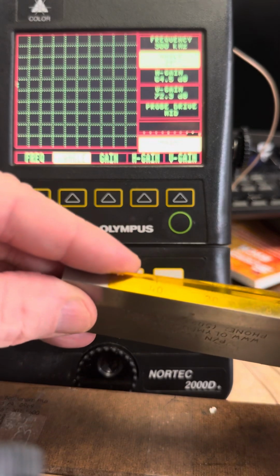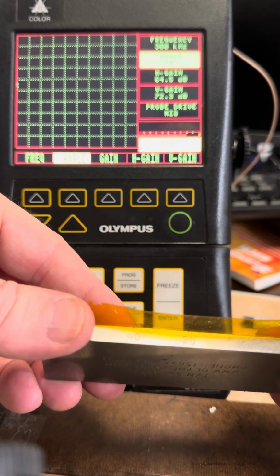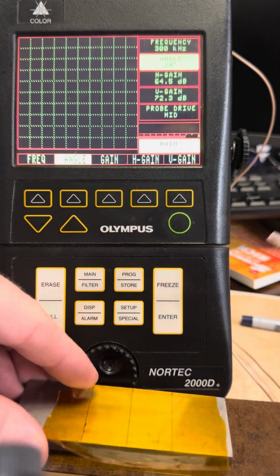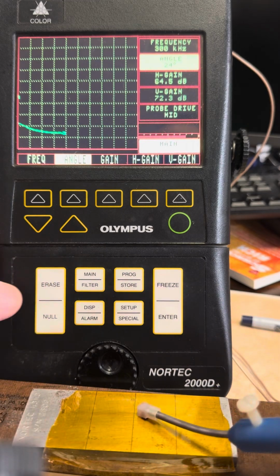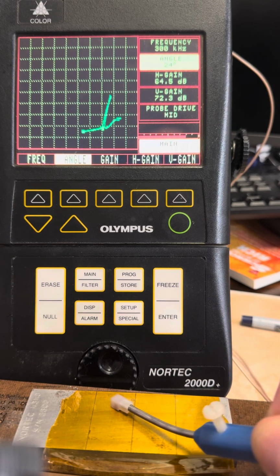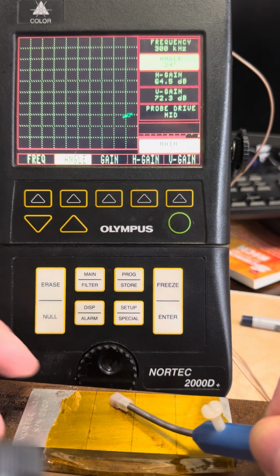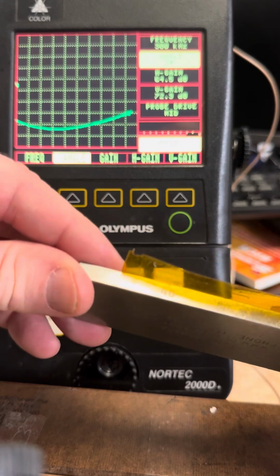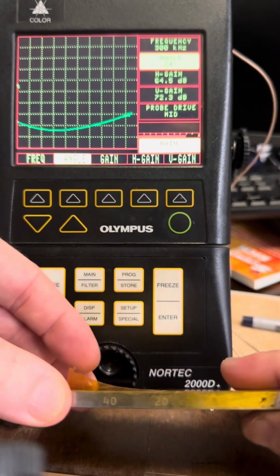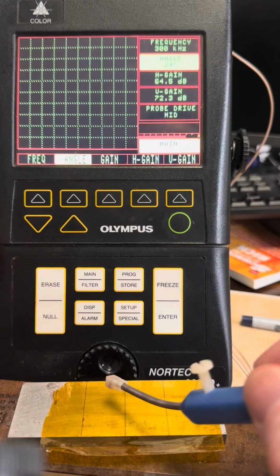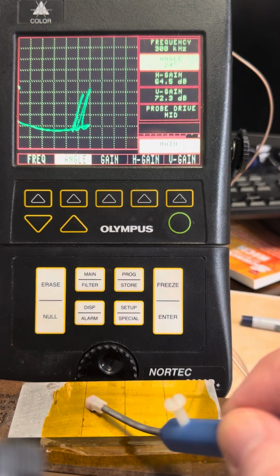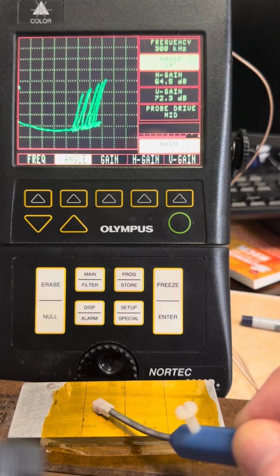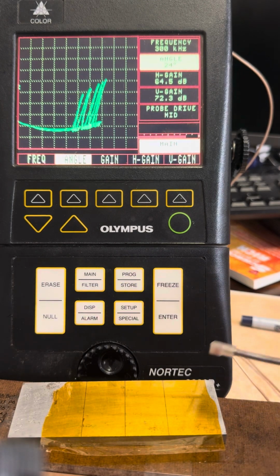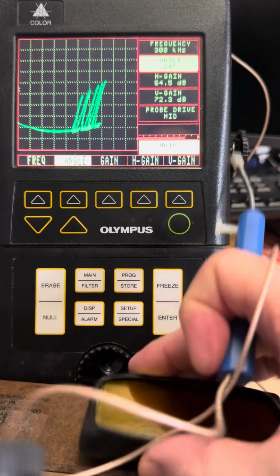The next one is 20 mils, so 0.020 inches deep. We're going to see what that looks like. So that's about 3 divisions. And then if I go over the deepest crack, which is 40 mils, 0.040 inches, that's going to give you a signal a little bit bigger, maybe 4 or 5. So that's the process.